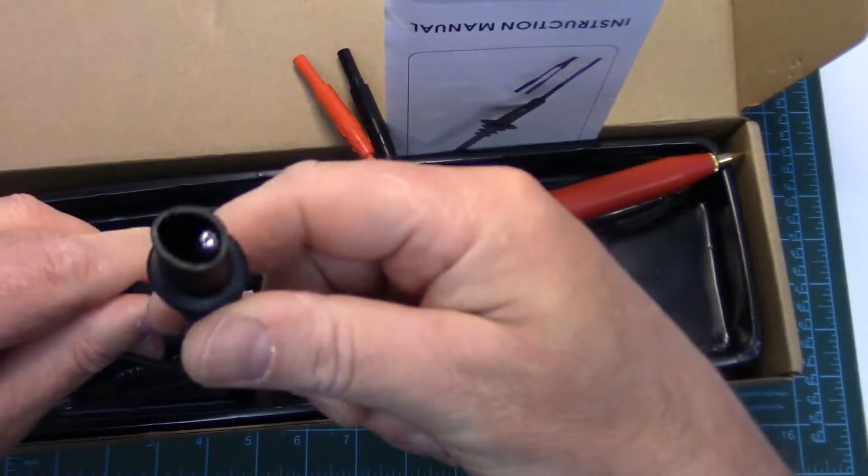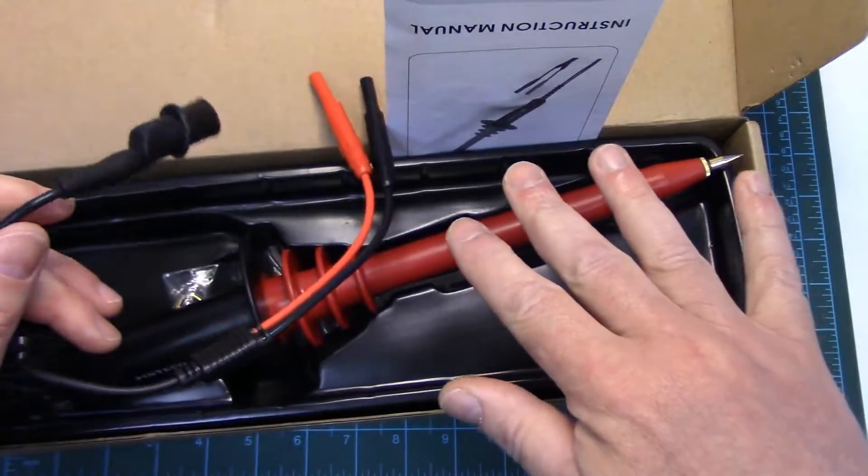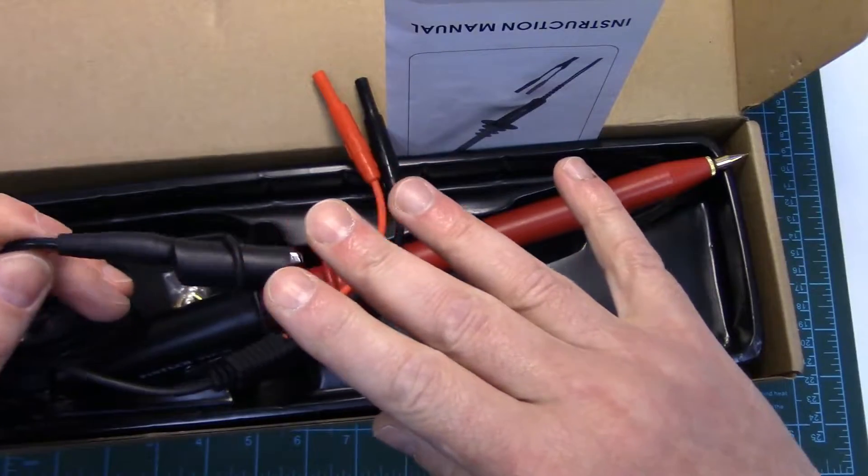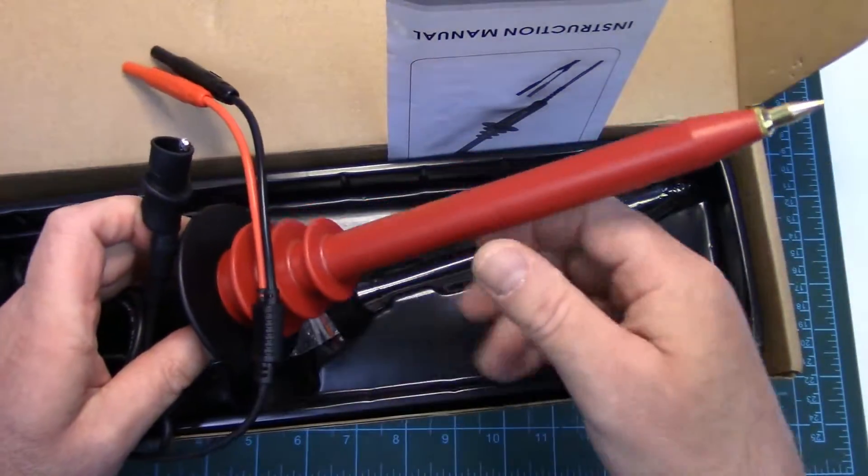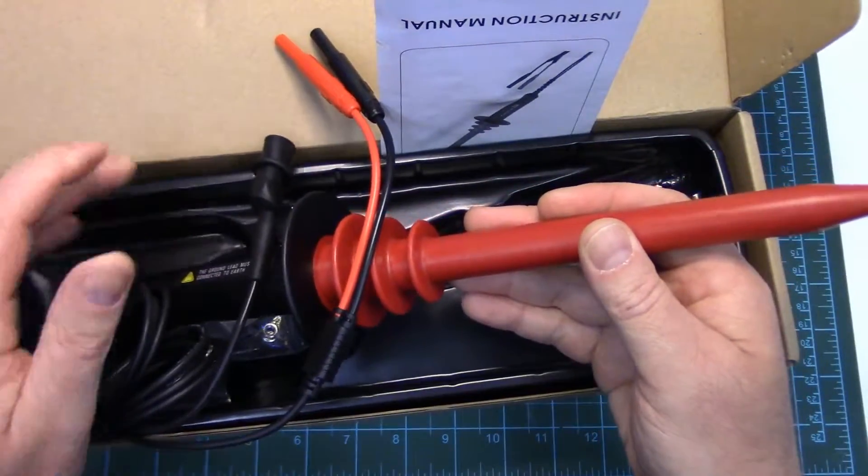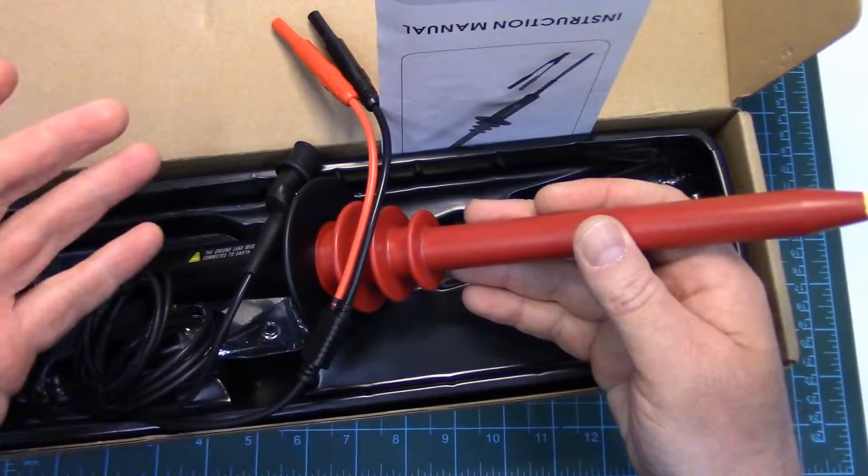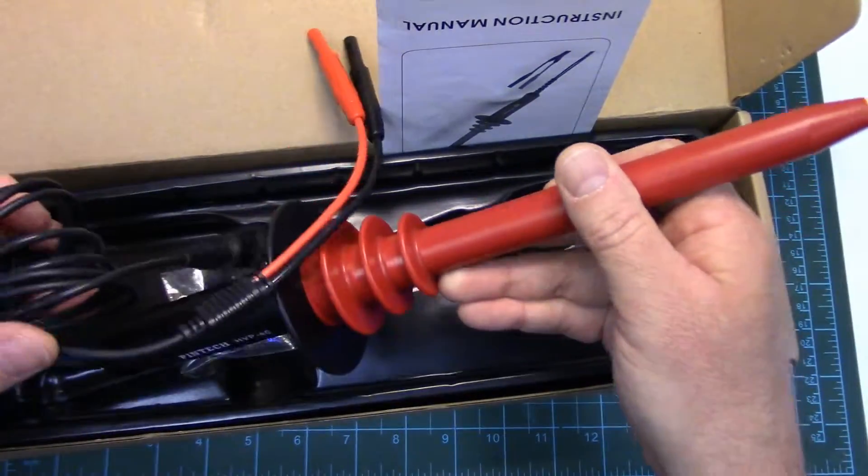And then the other wire on here is the grounding lead. And anytime you use one of these things, you're supposed to have this earth ground. So if any voltage did by chance arc past this into the circuit, it won't take out your multimeter. It'll go straight to ground and it'll also prevent you from getting a shock.